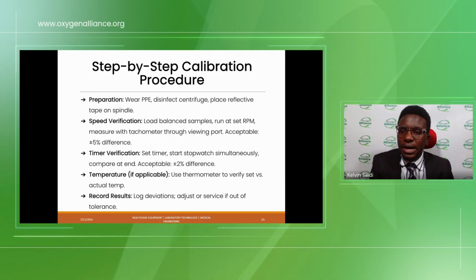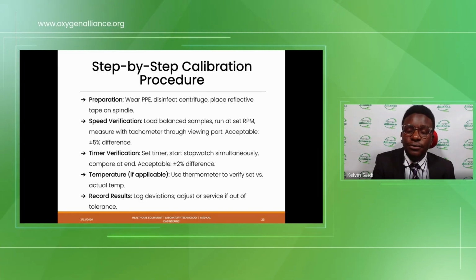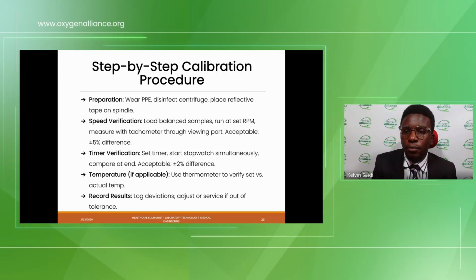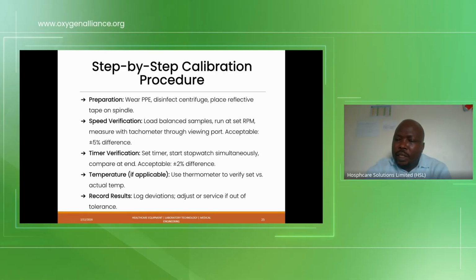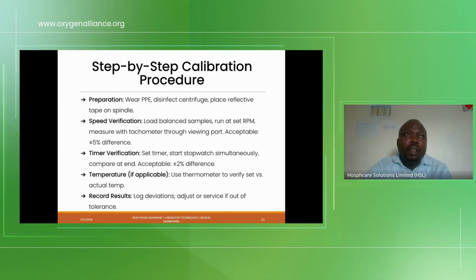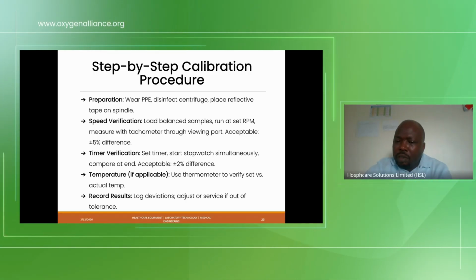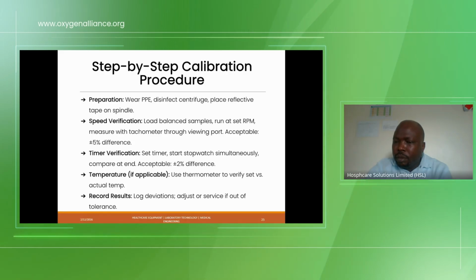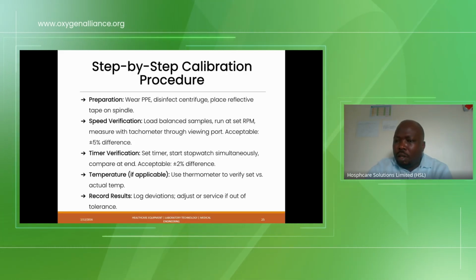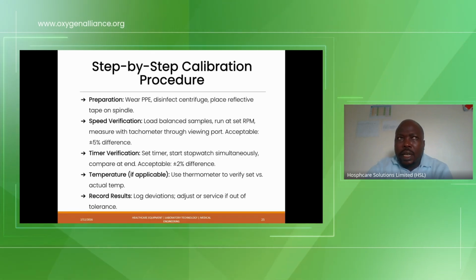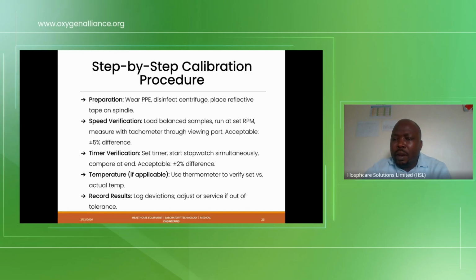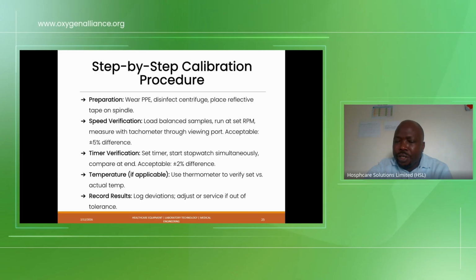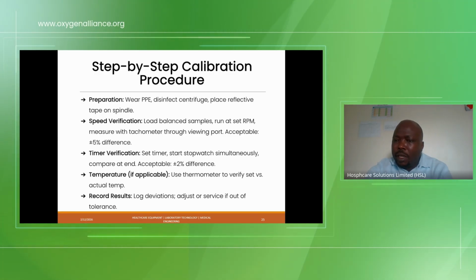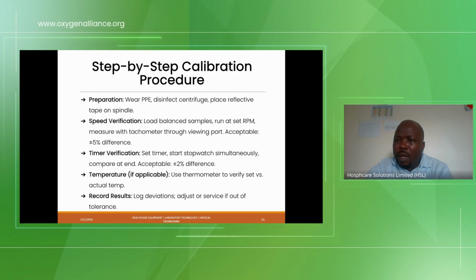Yes. So Victor asked, what could be the possible causes of centrifuge failure to reach the set RPM? Uncalibrated parameters. All right. There are so many factors that can lead to that. We can have a minimum operational output of the motors, probably as a result of mechanical damages. But the main one is uncalibrated parameters, so it doesn't reach the required RPM standard. So all these things revolve around calibration.